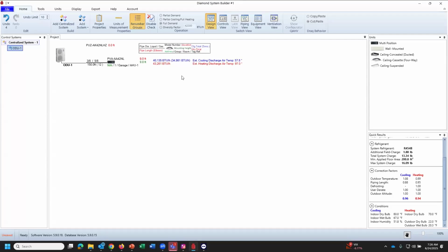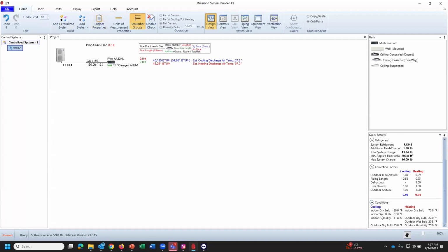On site visits, I wind up building a lot of these systems out whenever I'm in the field, looking to see if people are getting the BTUs out of the system that they should. Because if we're not getting the BTUs that we're calculating here, then we know we've got something else going on with the system. So we're going to go ahead and scratch this system at this point and take a look at a couple other scenarios.